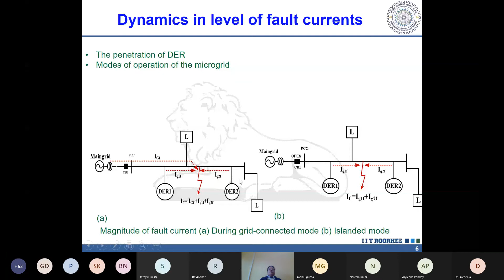The fault current direction also changes - even the pre-fault current direction changes with variation in the supply of renewable sources like solar and wind, and the grid terminals and storage devices. What is the meaning of bidirectional fault current in microgrid? This is the main grid, this is circuit breaker 1, and this is one feeder originating from the main substation through circuit breaker 2, which protects this particular feeder. In this feeder we have three laterals.